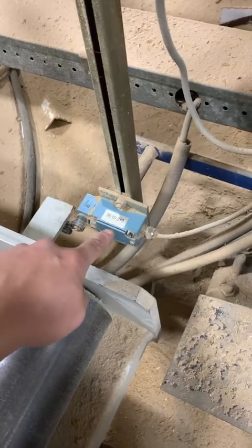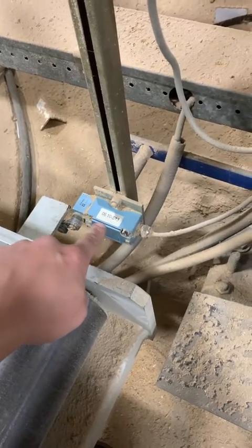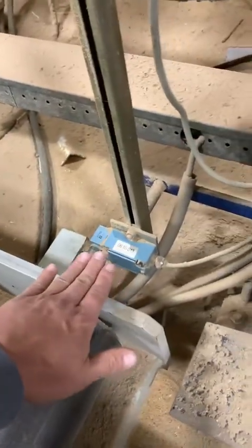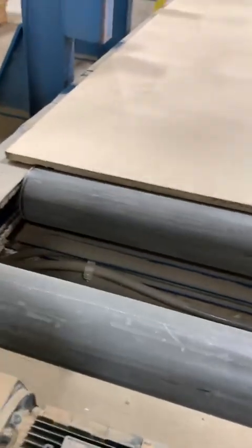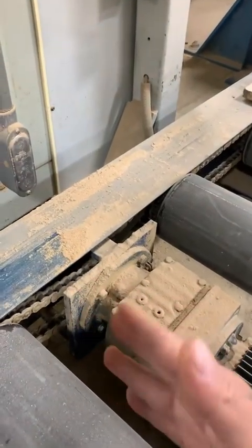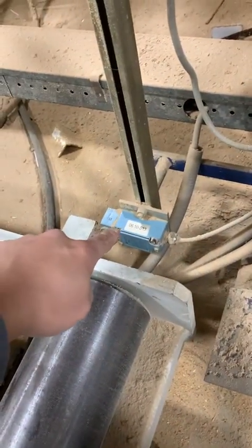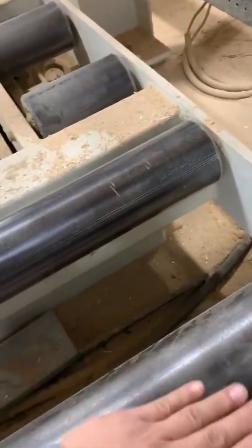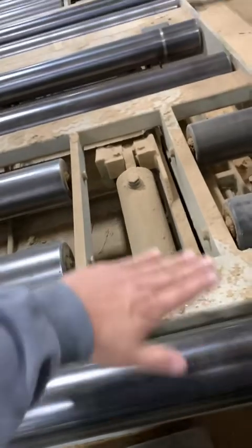If the PLC does not see that 24 volt input signal coming from this limit switch here, it would think that the roller table is not in the down position. So if we would have a board coming up, it would probably stop and it would just stall there. The sequence would not continue until that problem is fixed. Because if the PLC doesn't see that, it would think that it is either up or it is not down. And if they would send the board, it would crash into the table. The board would not make its way and set on the table.